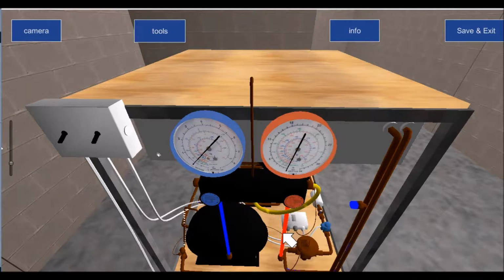But because of F-gas regulation, and because of our conscious awareness of global warming and ozone depletion, we're trying to encourage a practice whereby putting the gauges onto a system is a last resort, as opposed to a first resort. So when you're called to a job and asked to diagnose the problem because the customer tells you the system is not reaching temperature, it can be an air conditioning system for comfort cooling, a refrigeration system for chill, for ambient warm or high ambient temperature, or a freezer for low ambient temperature. It really doesn't matter, but if it contains F-gas, we want to prevent putting the gauges on, because that causes us to go through the process of purging. So we want to diagnose the problem in advance of putting on the gauges. Sometimes we might be able to diagnose the problem without ever putting a gauge line on the system. So that's the key message.